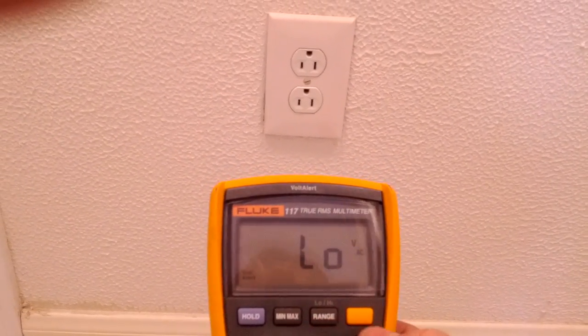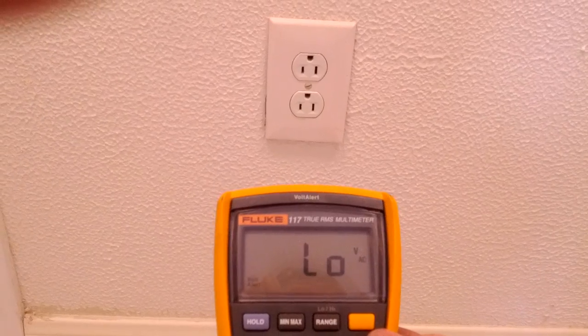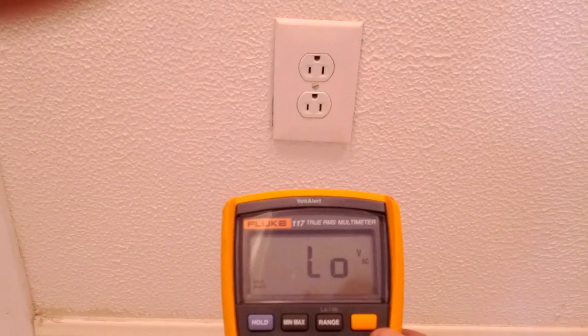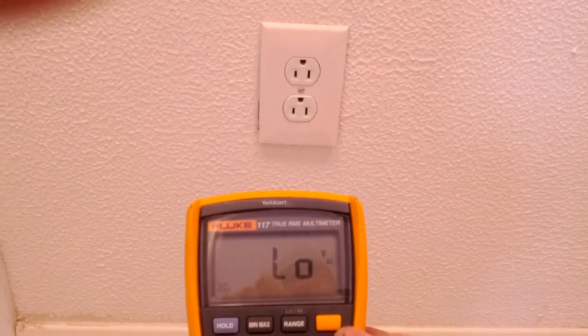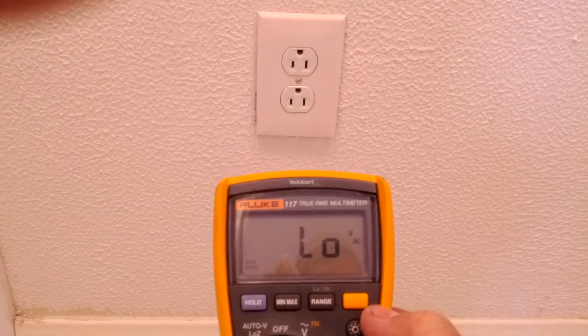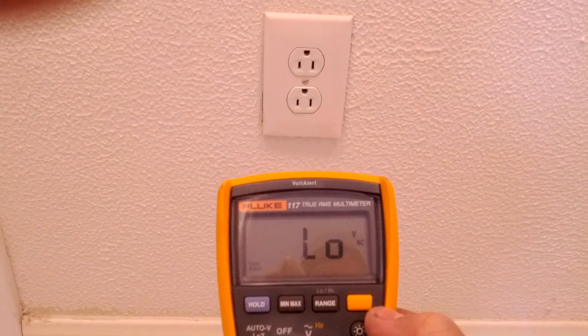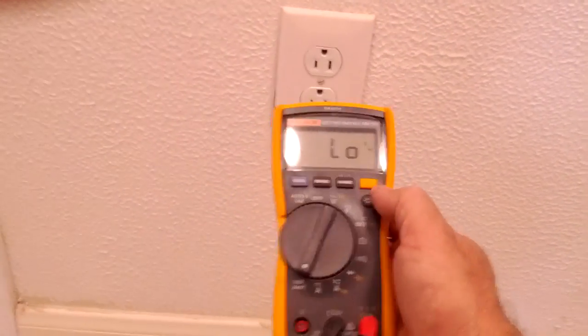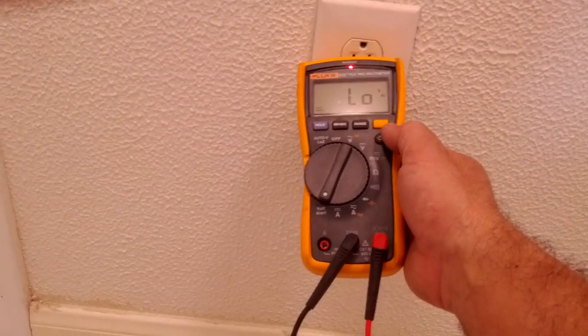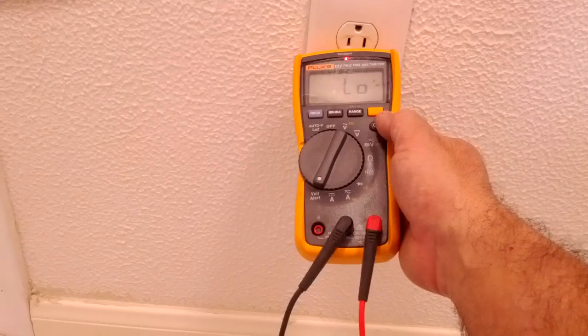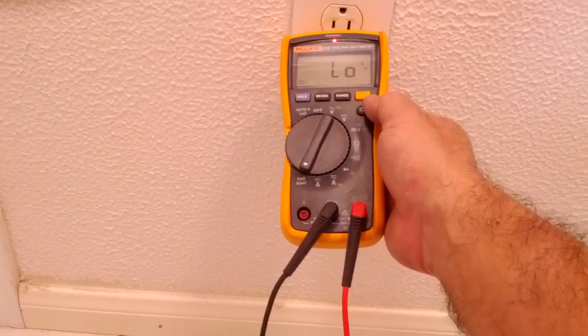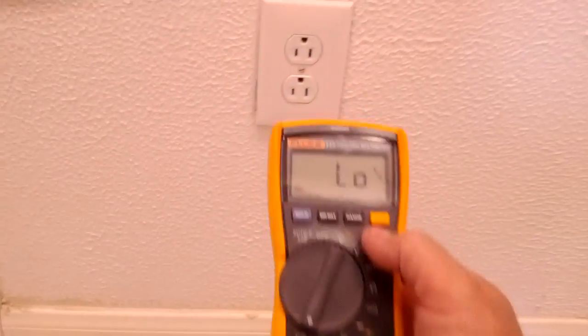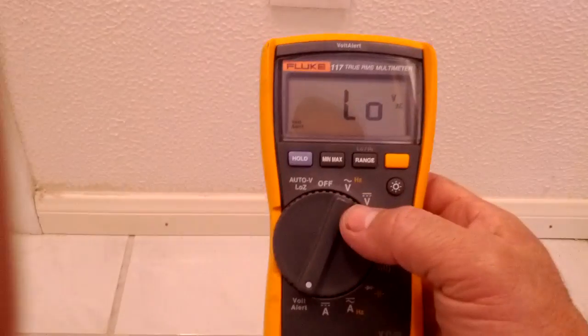The low setting is not so sensitive, so if you wanted to test a particular outlet or if you needed to get close to some wires without it going off too far away so that you can identify the wires that you're trying to test or the receptacle, it'll allow you to get closer, right up to about an inch, which is about where some of your sensitive non-contact voltage testers end up.